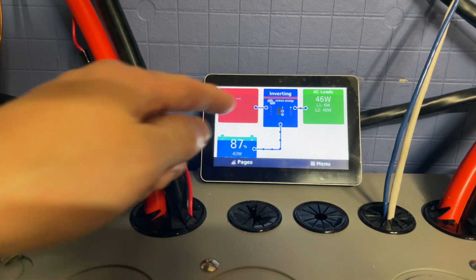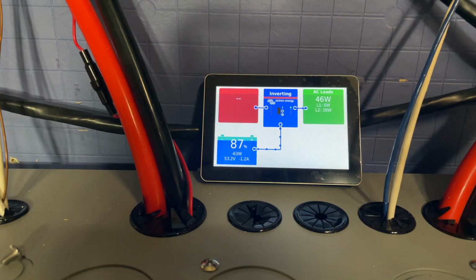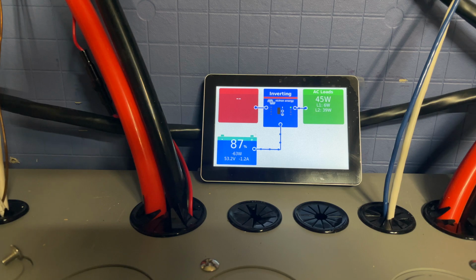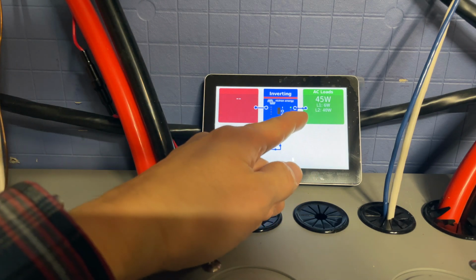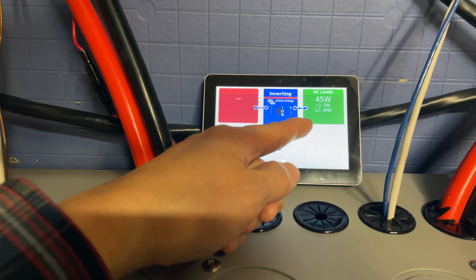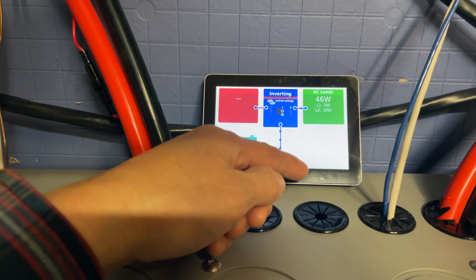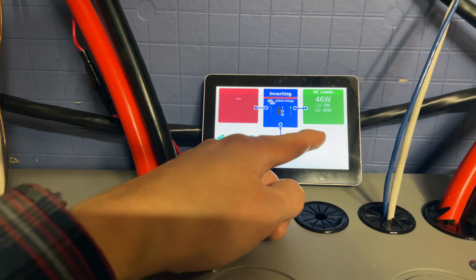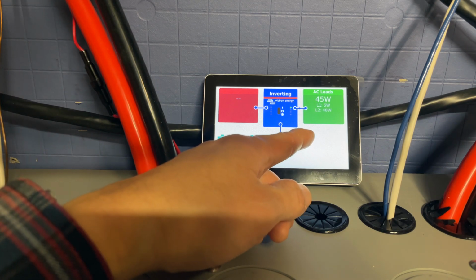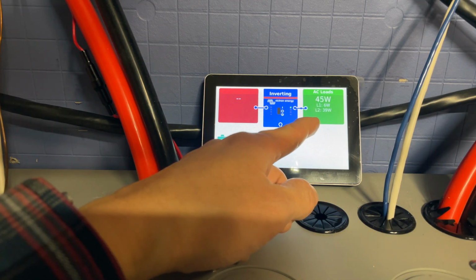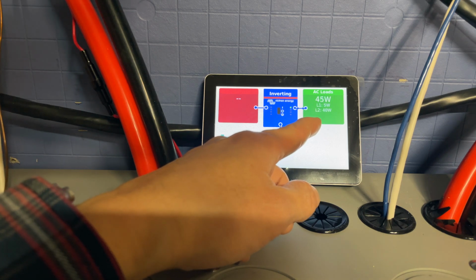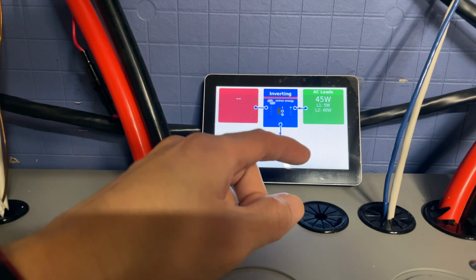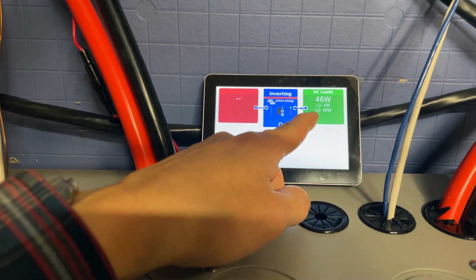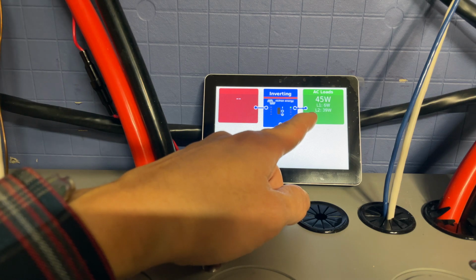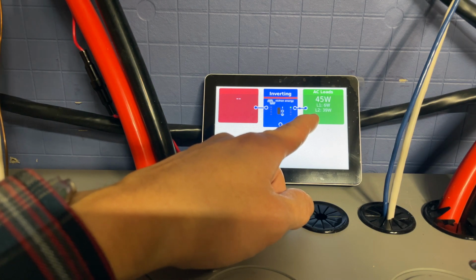I'll cover this quickly since some people worry about line balancing. On this type of system, because you have two transformer-based inverters set up for split phase, you don't have to worry about line balancing as much as you would with a high frequency single unit 240 volt split phase inverter, since those units use high frequency inverters and require balancing. In this type of system, you don't have to worry about it as much because the line limit is capped at the capacity for the smallest inverter, or any single inverter, since you have to use matching units.